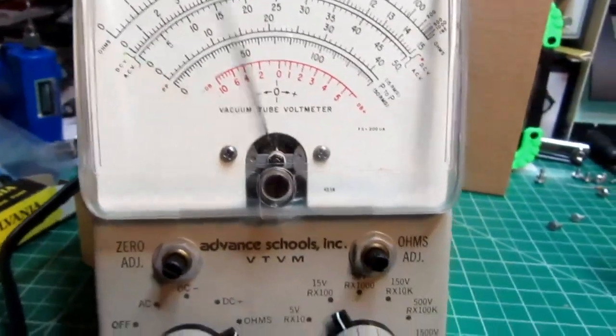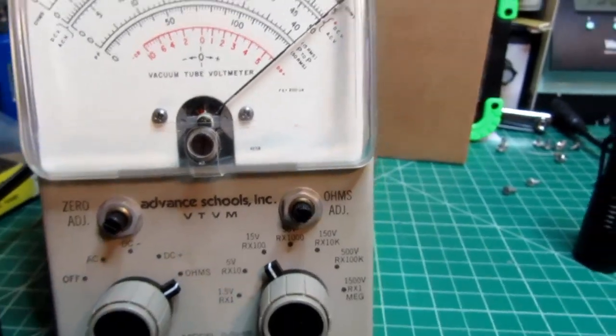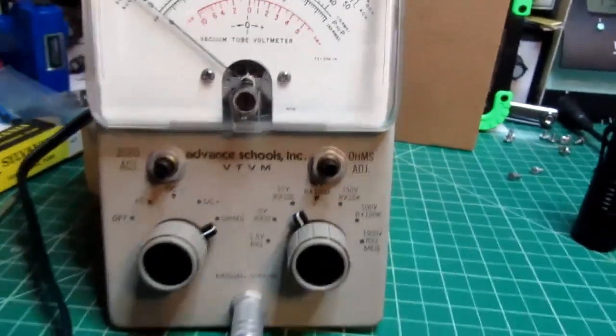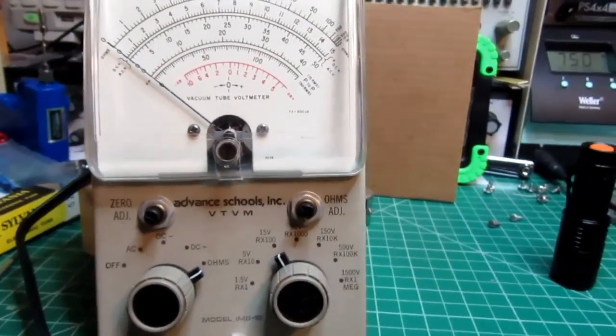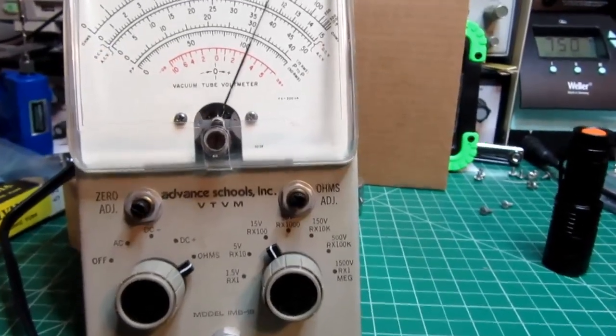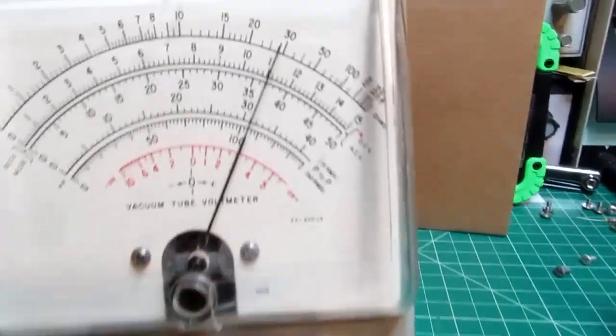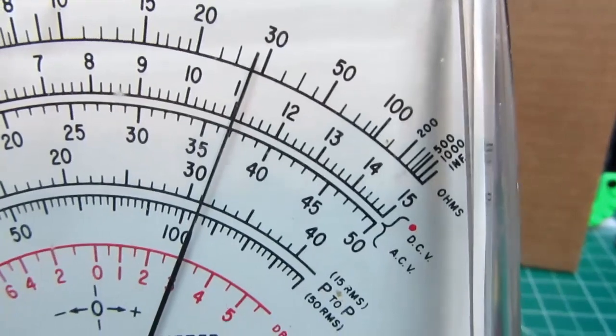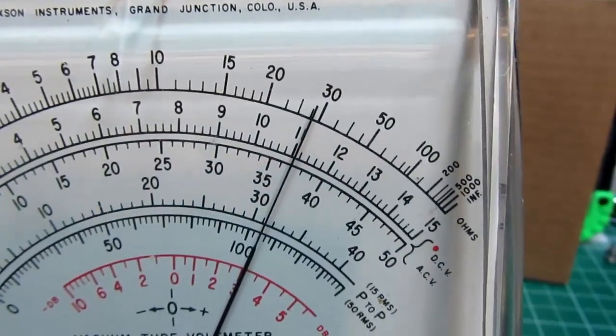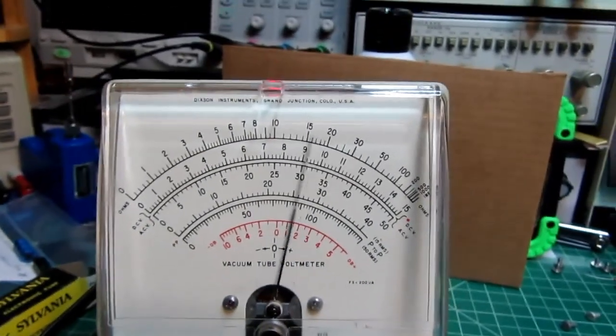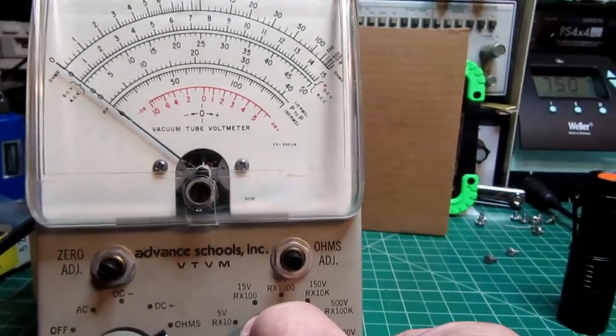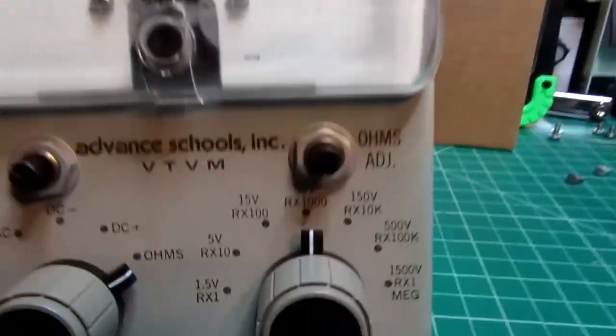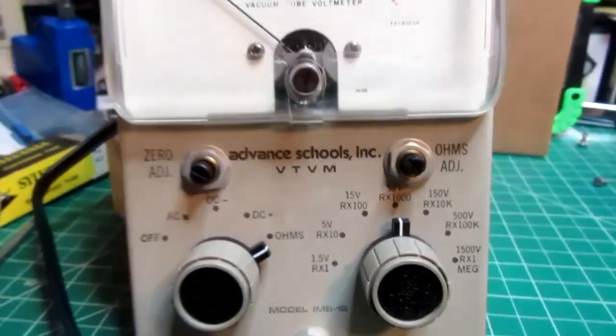Check my 0 and full scale. The 0 is looking pretty good. Full scale is looking pretty good. So I'll give it 3K, which is giving me 30 approximately on the meter, times 100 is 3K. So that's looking good. Let's go up to the R times 1K or R times 1000 range.